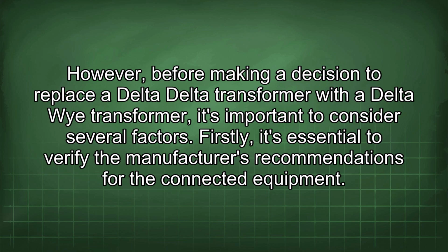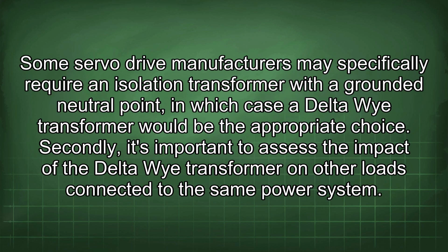However, before making a decision to replace a delta-delta transformer with a delta-Y transformer, it's important to consider several factors. Firstly, it's essential to verify the manufacturer's recommendations for the connected equipment. Some servo drive manufacturers may specifically require an isolation transformer with a grounded neutral point, in which case a delta-Y transformer would be the appropriate choice.